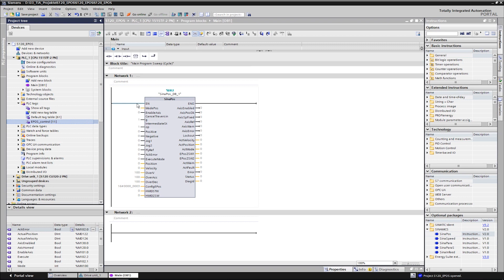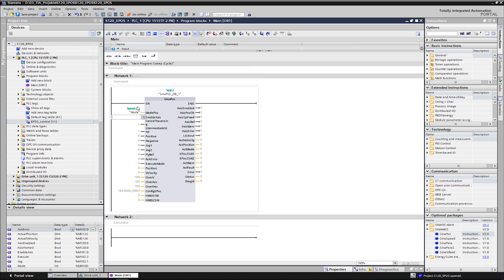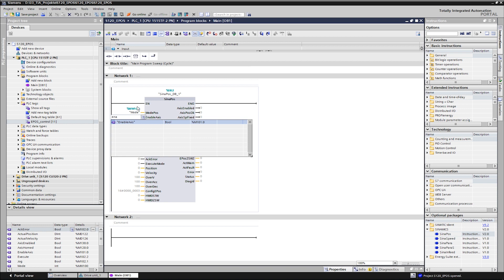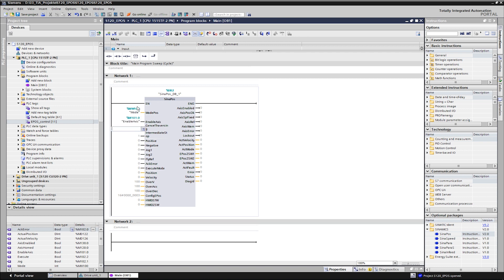We start with the mode input to select the different operating modes of the basic positioner. The enable axis input is used to switch the drive on and off. Cancel traversing means discarding and cancelling a motion task and must have a one signal for positioning to be performed as it is switched to low active. The same applies to intermediate stop, which is used for the intermediate stop function.